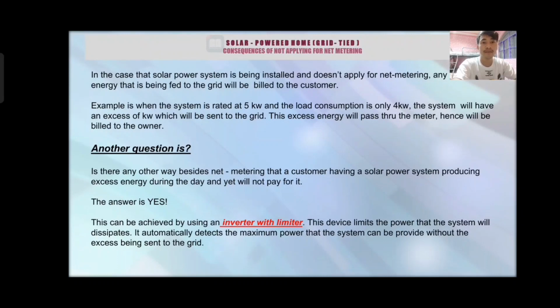Is there any other way besides net metering for a customer with a solar power system producing excess energy during the day to not pay for it? The answer is yes. This can be achieved by using an inverter with a limiter. This device limits the power that the system will dissipate. It automatically detects the maximum power that the system can provide without the excess being sent to the grid.